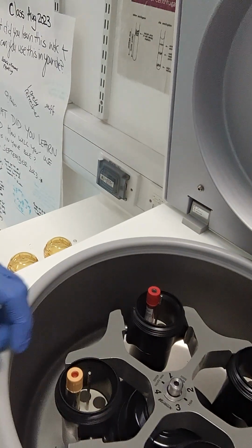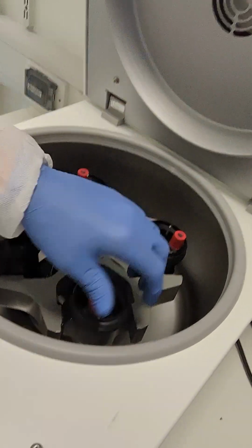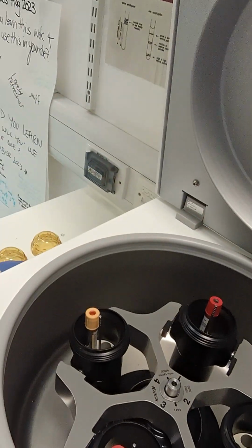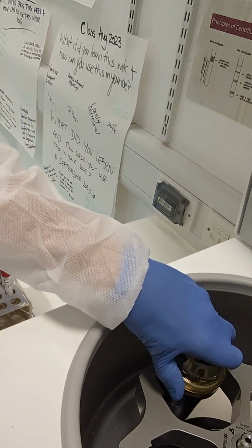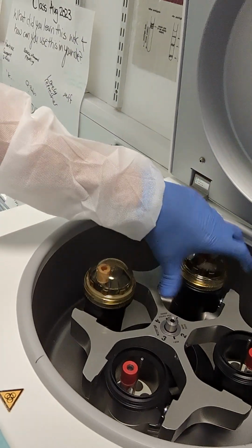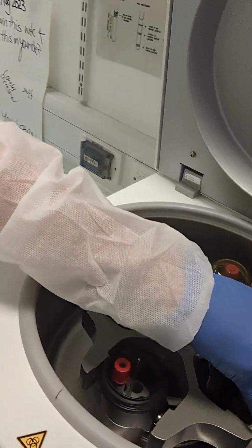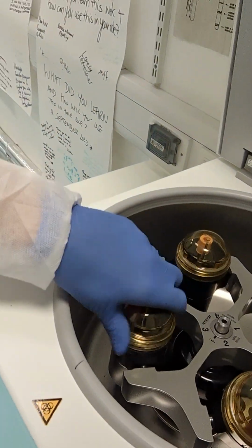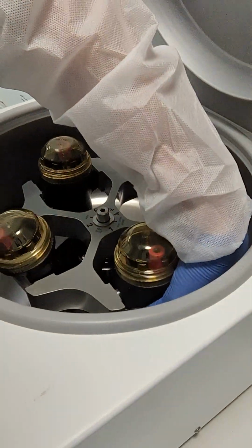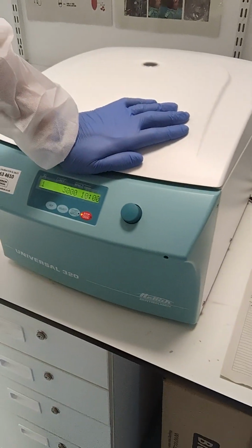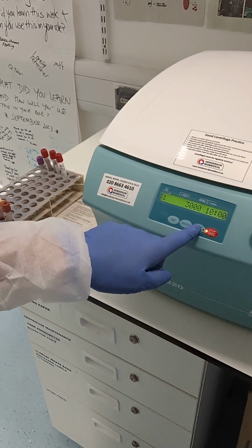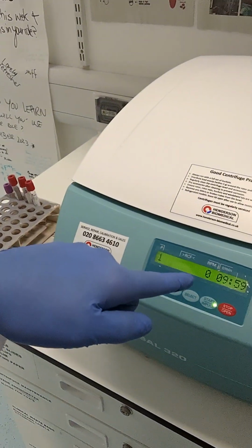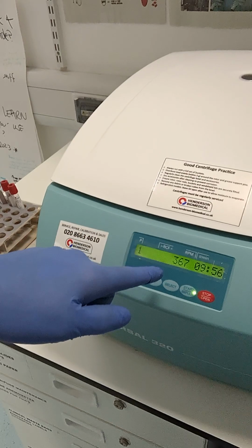We've balanced the centrifuge. We check our buckets can rotate on their bracket. We place biolids firmly on the centrifuge. We check the rotor for debris. We close the lid. And we press start. And the centrifuge will display the countdown and the RPM going up. The centrifuge will run for 10 minutes. It will vibrate slightly, make a slight noise, but that's fine.